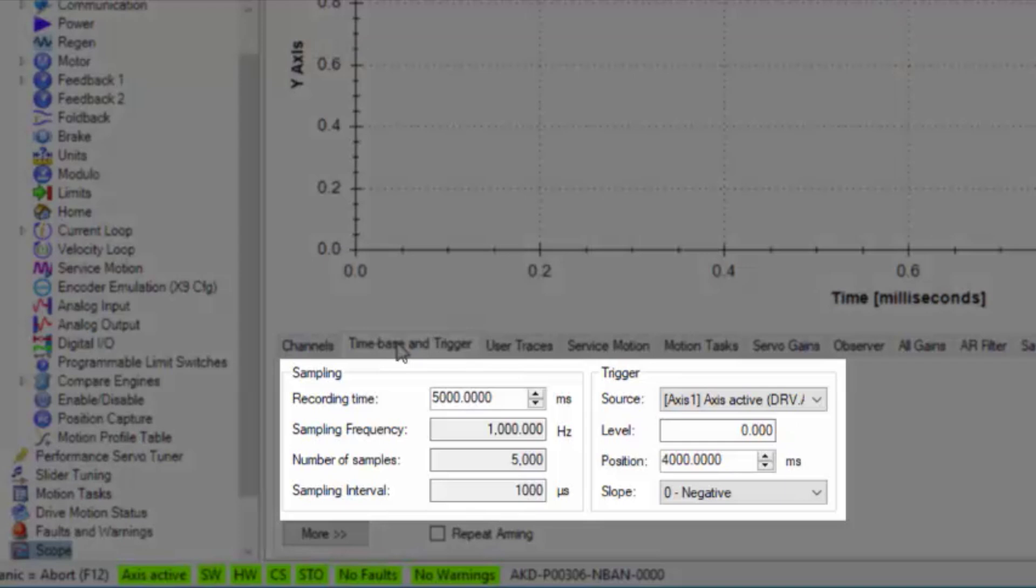The trigger source is set to drive active, the level is set to zero and the slope is set to negative since we will see the drive active going to zero when a fault has occurred.